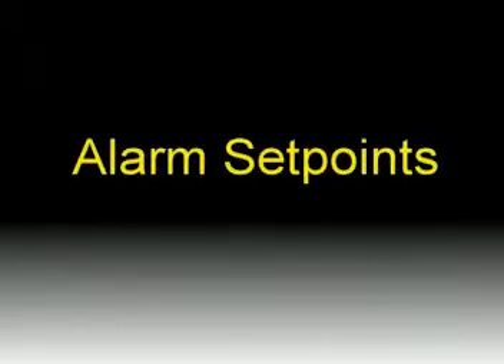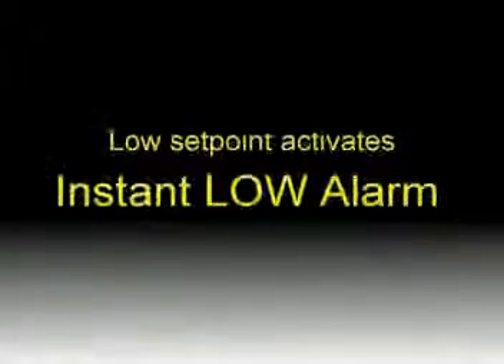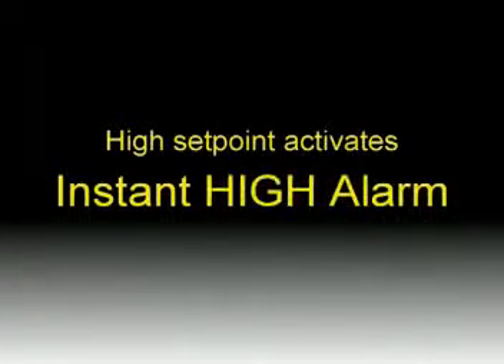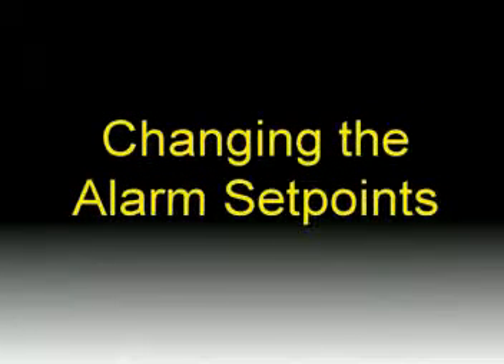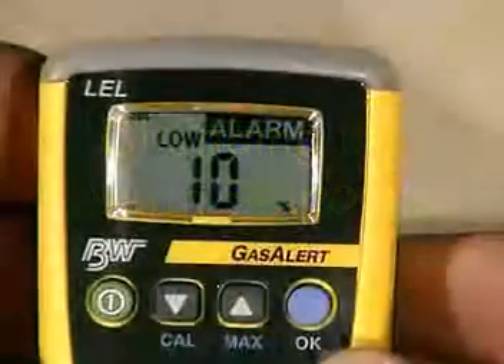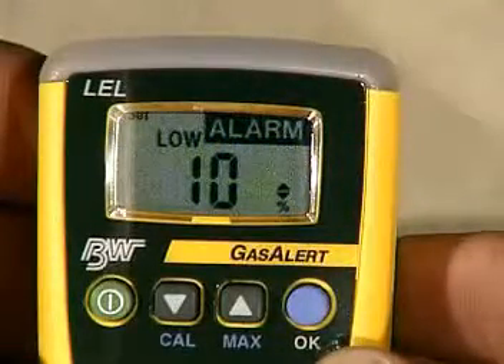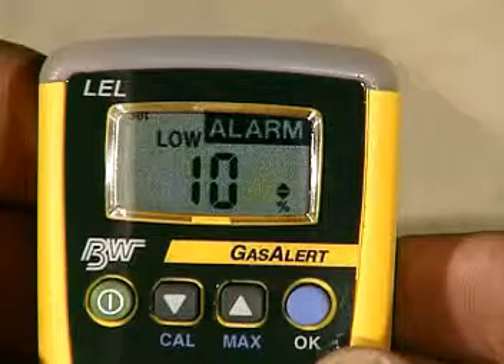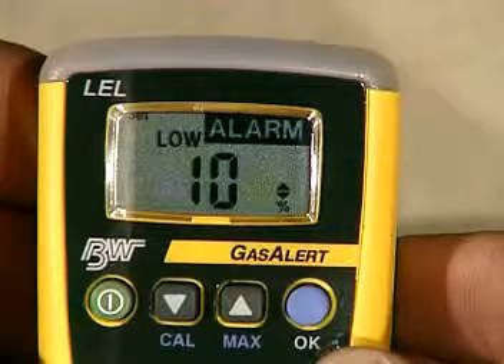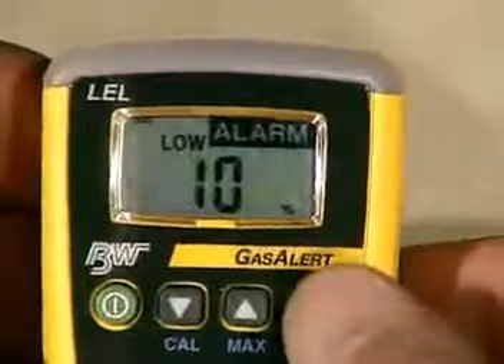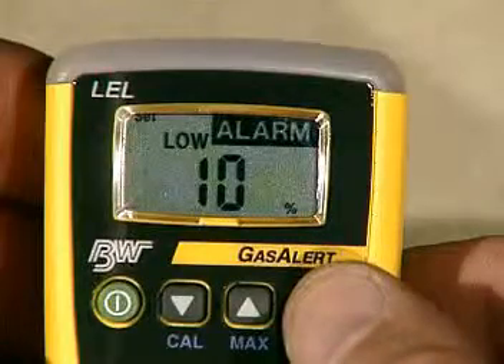GasAlert-LEL has 2 gas alarm set points. The low set point activates instant low alarm. The high set point activates instant high alarm. You may change the alarm set points after calibration is complete. The screen will read Set Low Alarm and will display the current low alarm set point. Change the set point using the up-down arrows. Let's press OK to save the displayed value.